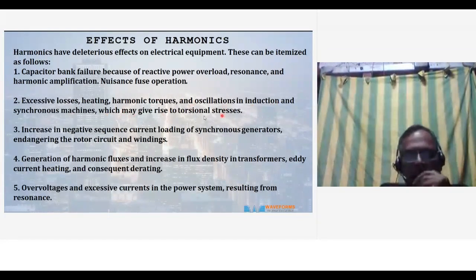So what happens is, in motors driven by a drive, there's a fifth harmonic component which is a negative sequence, so the magnetic flux tends to be in reverse. The positive and negative cause a torsional vibration, and you have bearing failures, insulation failures, and the premature failure of the motor itself. An increase in negative sequence current loading of synchronous generators endangers the rotor circuit and windings. The same harmonic causes all these problems.